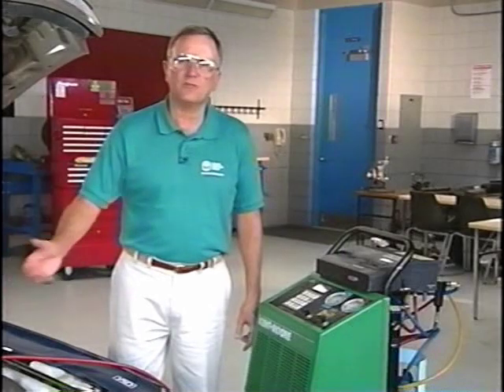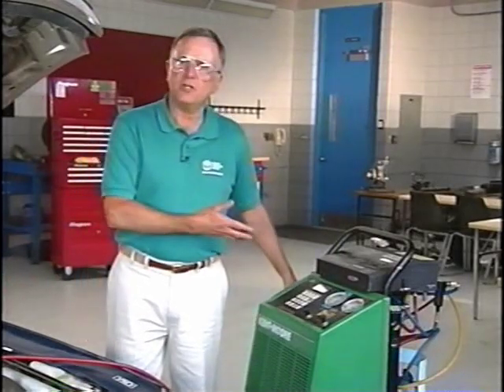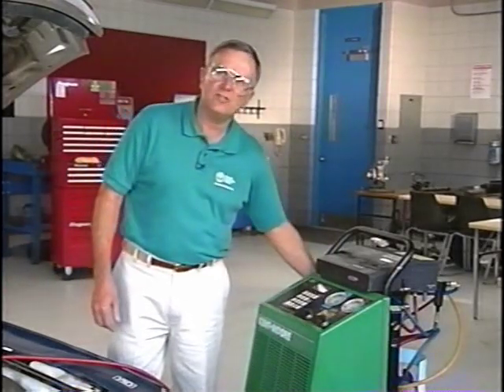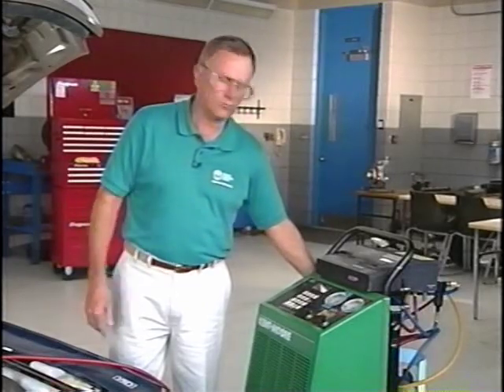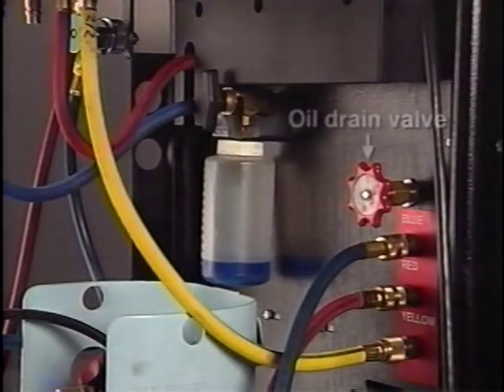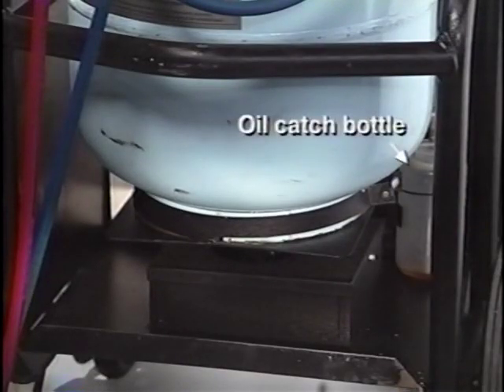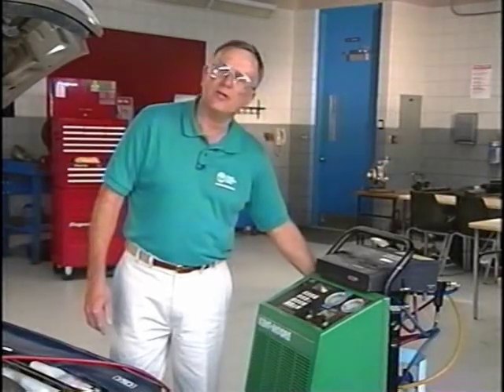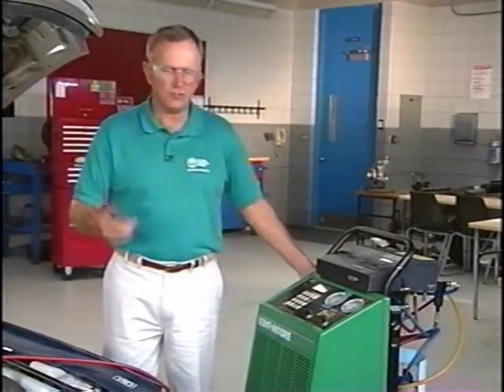Now that we have all our service lines connected, we'd like to go to the ACR4 and check to see if there's any oil left from the previous repair. Slowly open the oil drain valve to check if the oil separator contains oil. Allow any oil to drain into the catch bottle. In this case right here, there is no oil, so we'd like to continue on.